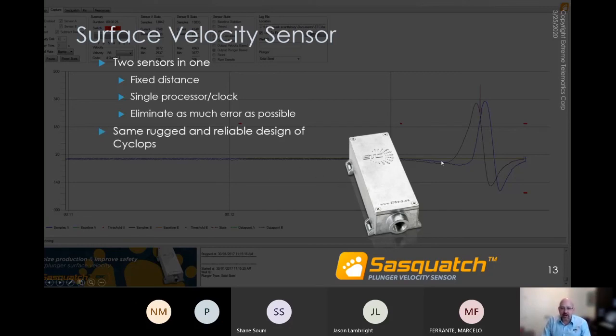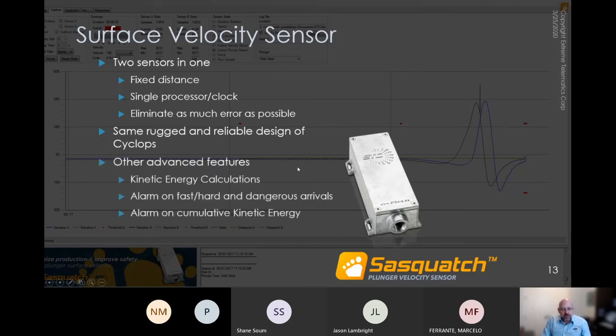You can see it in the background here, we actually have 2 waveforms and they're offset by time. So what we do is we actually look at some inflection points in this, the peaks and valleys, crossing the thresholds, and we correlate these two waveforms in time to get an average time between plunger arrivals, and then we use that to calculate the velocity at surface.